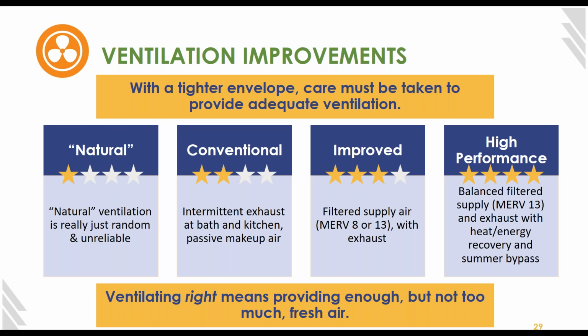So we can do improved ventilation with filtered supply air and with controlled exhaust to provide a more predictable, higher quality ventilation scenario for our residents. And then as a step beyond that, we have a high performance ventilation approach where we do balanced and filtered supply air and exhaust with heat or energy recovery and summer bypass. So that was a lot of words.